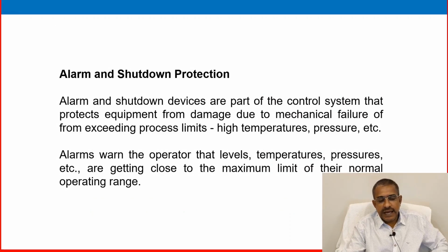The other thing is alarm and shutdown protection. Alarm and shutdown devices are part of the control system that protect the equipment from damage due to mechanical failure, and from exceeding process limits like high temperature and high pressure. Other than that, various other parameters as well. Alarms warn the operator that level, temperature and pressure etc. are getting close to the maximum limit of their normal operating range.